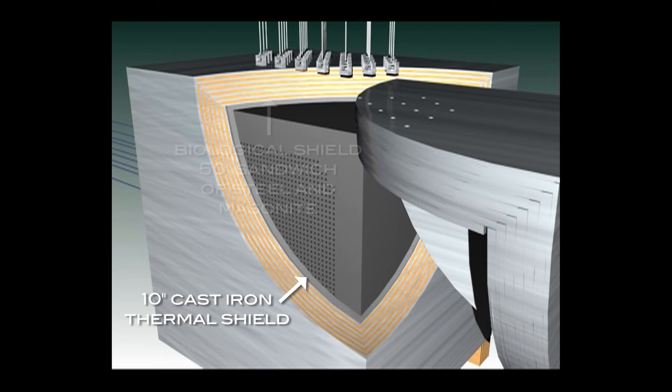The next shield barrier is a 50-inch sandwich of steel and masonite. The hydrogen atoms in the masonite slow down escaping fast neutrons, and the steel captures the remaining slow neutrons in gamma rays. This combined shield arrangement has the same shielding capacity of 15 feet of concrete and makes it possible for workers to safely be in the work area when the reactor is operating.